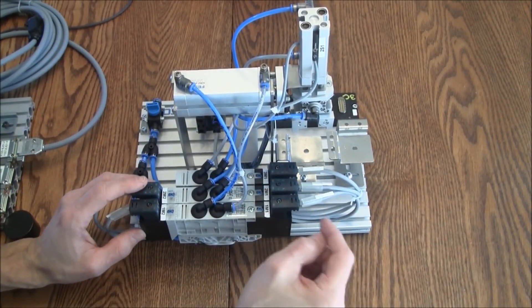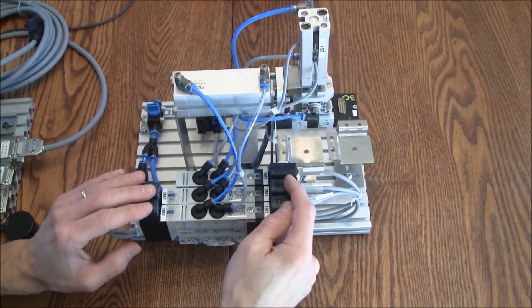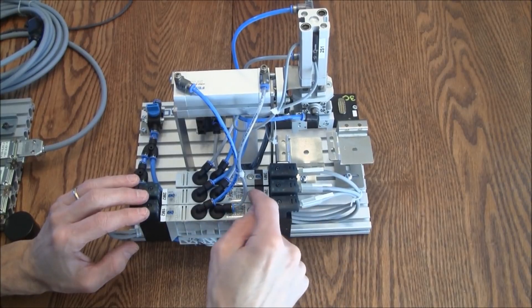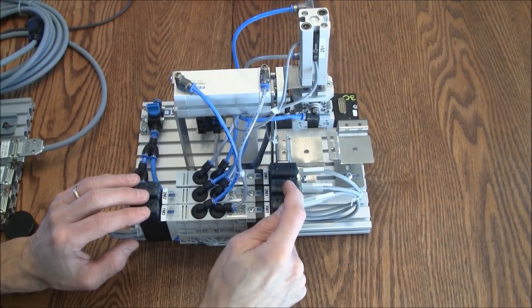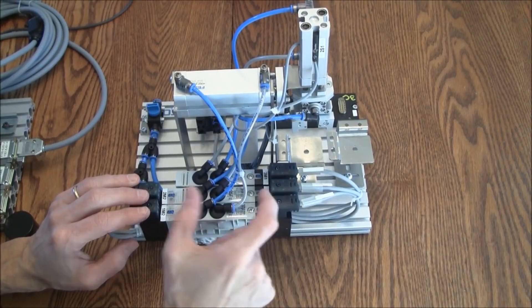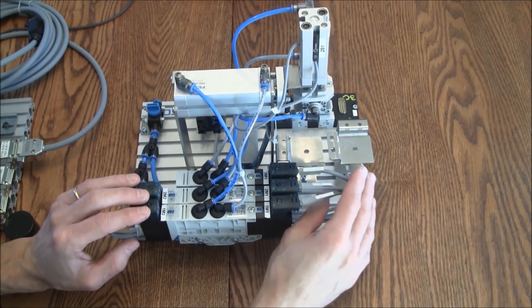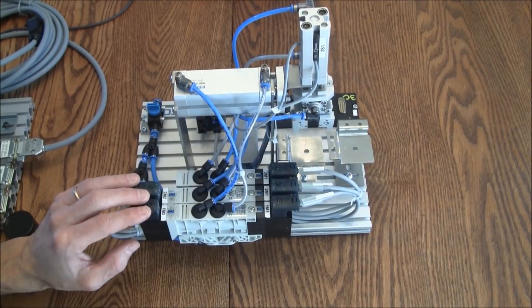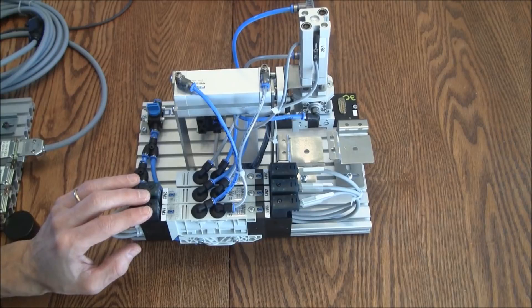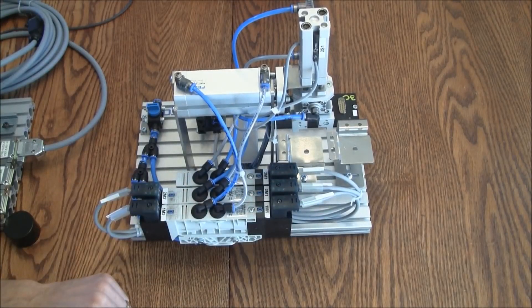There are reasons. Sometimes the program is a little bit easier to use the double versus the single. Sometimes you want to maintain that detented feature where I don't have to keep this energized all the time in order to keep the valve in that particular position. So if there were a power failure and I would lose power to my PLC and coils, I don't have to worry about the machine moving into some other position. It'll hold that position. That could be for safety reasons. So there's a number of reasons why we may have this configured the way it is.